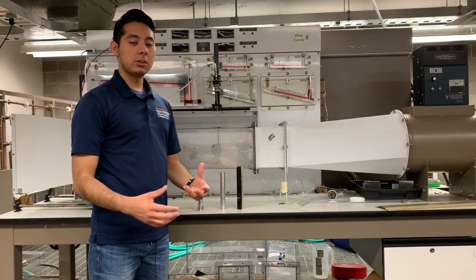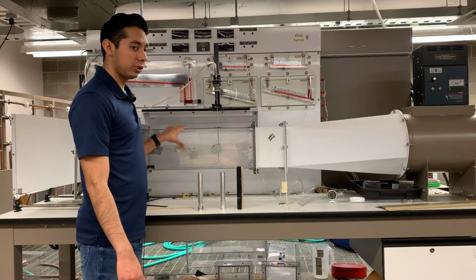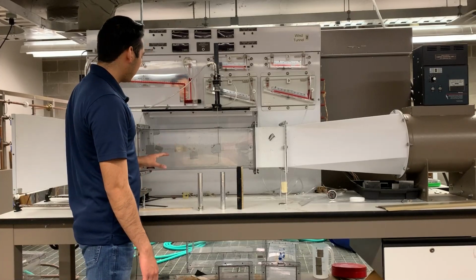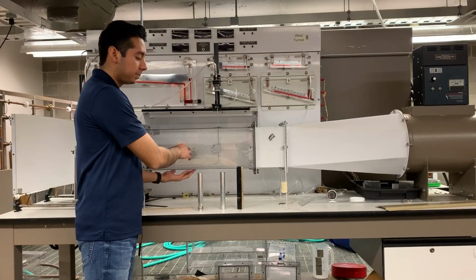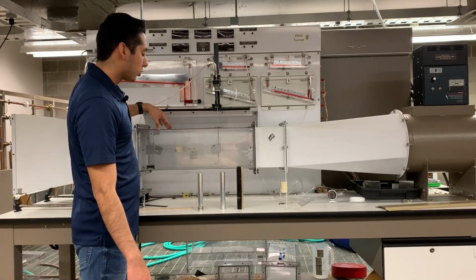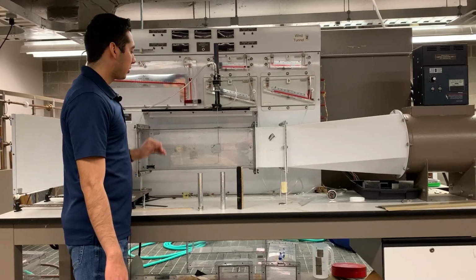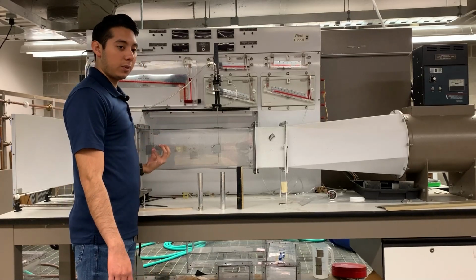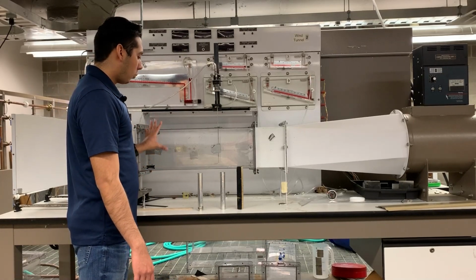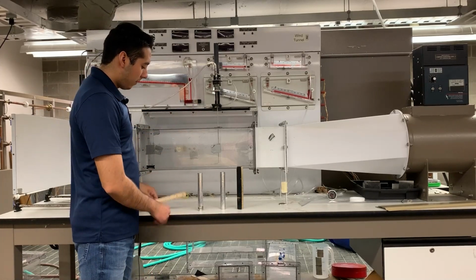So the first part of the procedure is to put one of these rods inside the duct, and we need to screw them over here in the middle. And once we do that, we're going to put our pitot tube through this hole over here in the front, all the way to the middle of the duct, so that we can measure the pressure at the entrance of the duct.